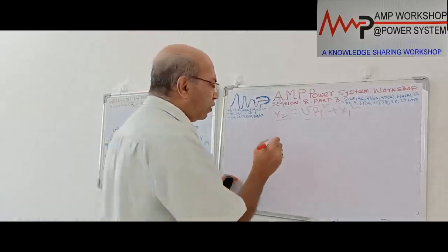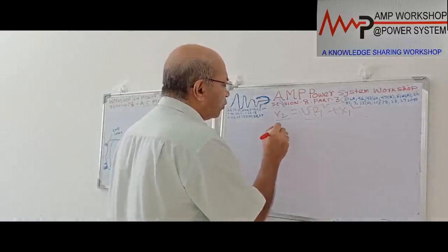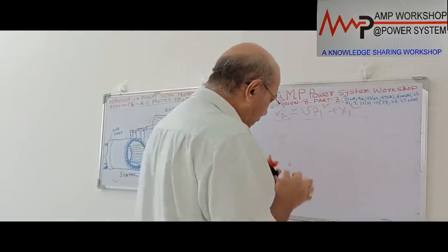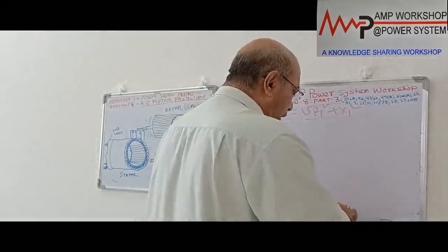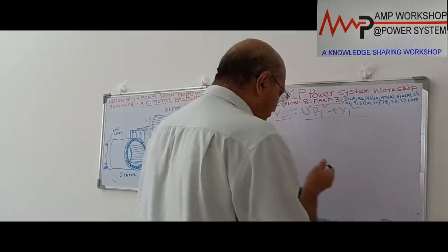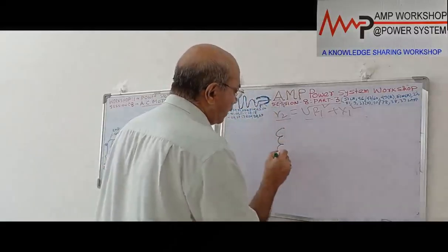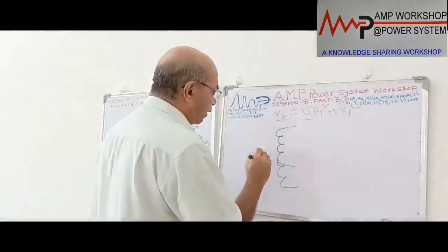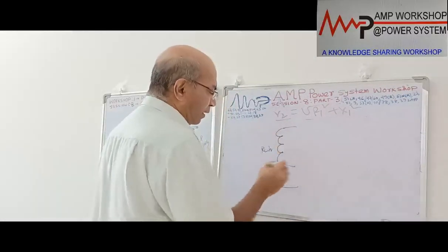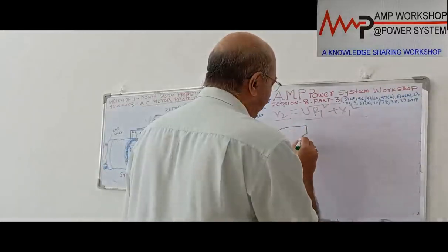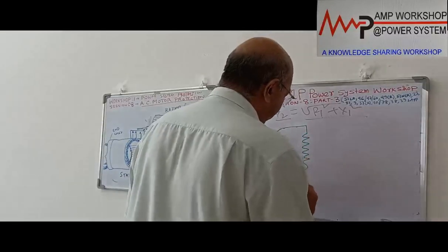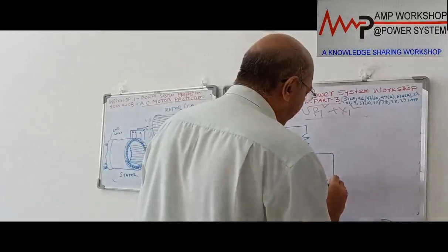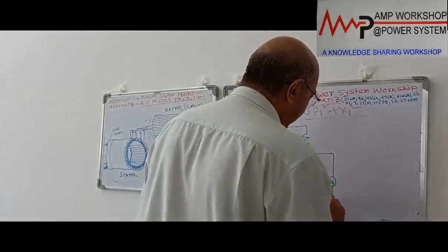The same thing we can do in case of a synchronous motor, for the field or exciter winding. The field winding has a DC supply, a positive DC supply coming through the slip ring. We have seen this is your rotor field. In case of an AC synchronous motor, we put a resistance or potentiometer over here, tap off the center point of the potentiometer, and then connect a 64 earth fault relay over here to ground.